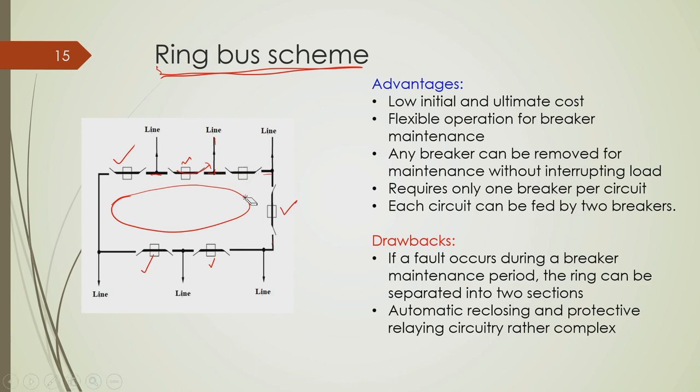Okay. So, this is possible, and here also, if you need maintenance of any breaker, then there will be no interruption of any feeder. So, I need to do the maintenance of that breaker. I could simply disconnect it, and this will not interrupt the whole circuit, because this will just break the loop and this will keep all the lines energized. Okay. So, that is the advantage.